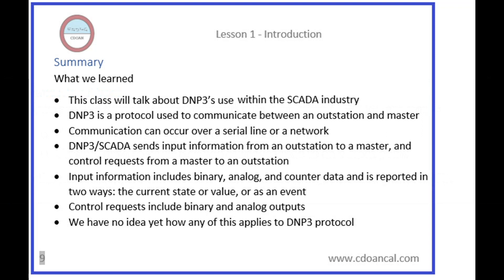So that's the end of this brief introductory lesson. What have we learned? This class will talk about DNP3's use within the SCADA industry. DNP3 is a protocol used to communicate between an outstation and master. Communication can occur over a serial line or a network. DNP3 SCADA sends input information from an outstation to a master, and control requests from a master to an outstation. Input information includes binary, analog, and counter data, and is reported in two ways: the current state or value, or as an event. Control requests include binary and analog outputs.